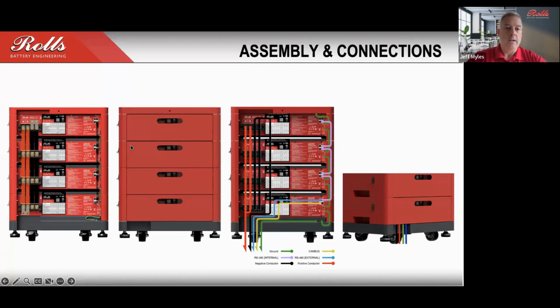You'll note on the back that it looks like it has a handle cut out. That actually is a dual purpose. It does allow you to remove that panel if you need to, but it also provides visibility for the UL, in our case, Intertek logo. That is a requirement for UL 9540 that all of those certifications need to be accessible and visible for inspection.